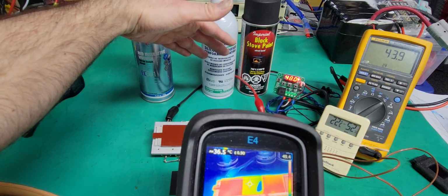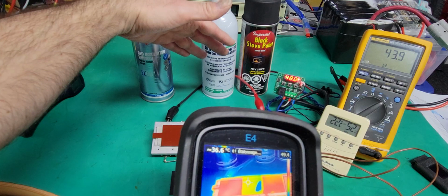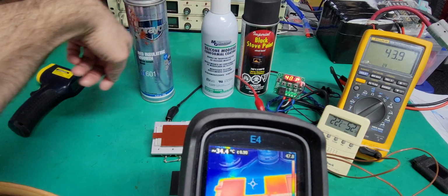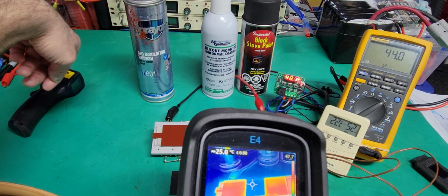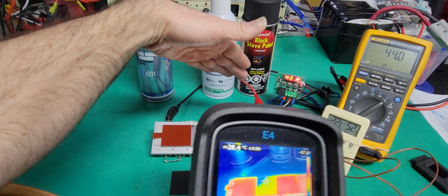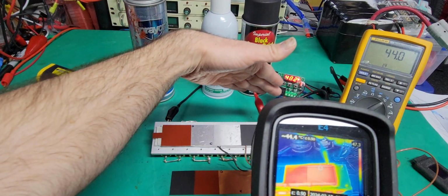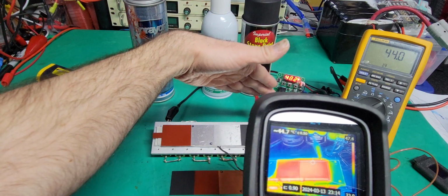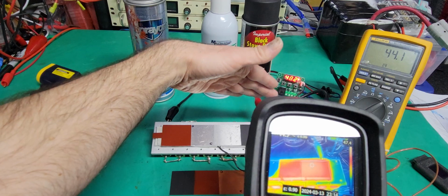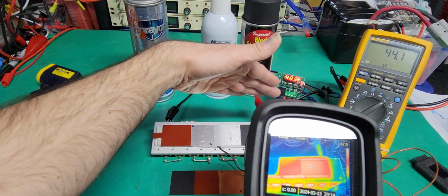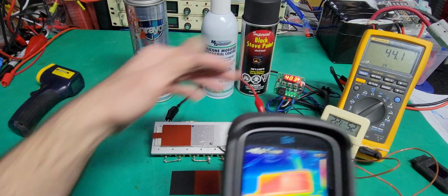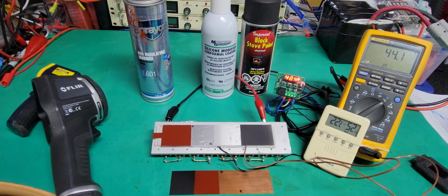You see the temperature changing, it reads 36 degrees just because of my hand. If I remove it, you see 24. So that's why it's important to have a very good coating when you want to measure temperature. Normally plastic will respond great, have good emissivity like 0.8 or 0.9, but I will give you a good trick.